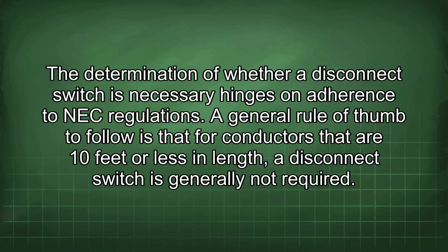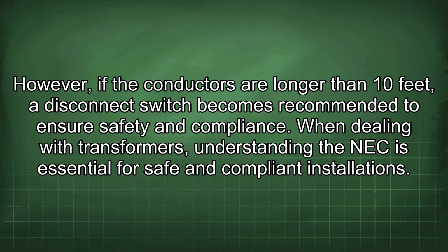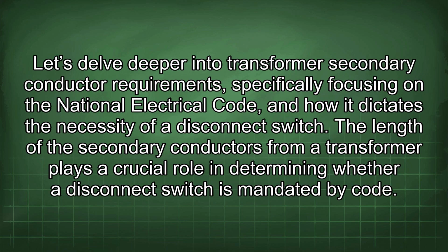A general rule of thumb to follow is that for conductors that are 10 feet or less in length, a disconnect switch is generally not required. However, if the conductors are longer than 10 feet, a disconnect switch becomes recommended to ensure safety and compliance. When dealing with transformers, understanding the NEC is essential for safe and compliant installations. Let's delve deeper into transformer secondary conductor requirements, specifically focusing on the National Electrical Code and how it dictates the necessity of a disconnect switch.